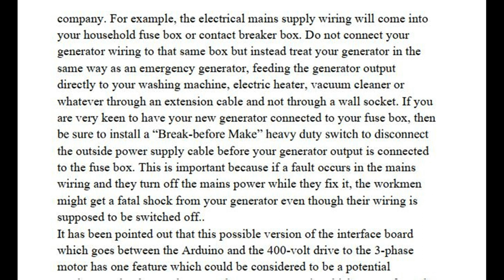If you are very keen to have your new generator connected to your fuse box, be sure to install a break-before-make heavy-duty switch to disconnect the outside power supply cable before your generator output is connected to the fuse box. This is important because if a fault occurs in the mains wiring and they turn off the mains power to fix it, the workman might get a fatal shock from your generator even though their wiring is supposed to be switched off.